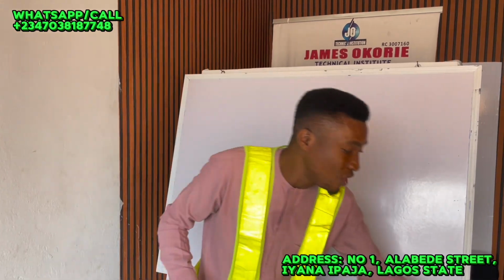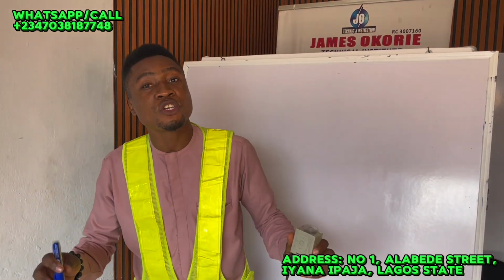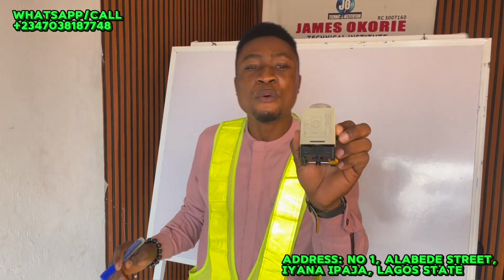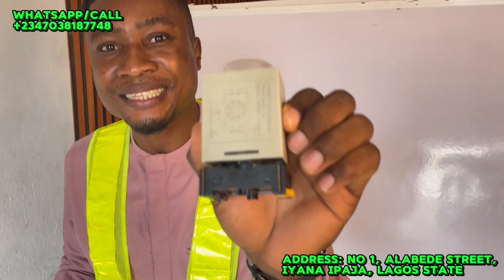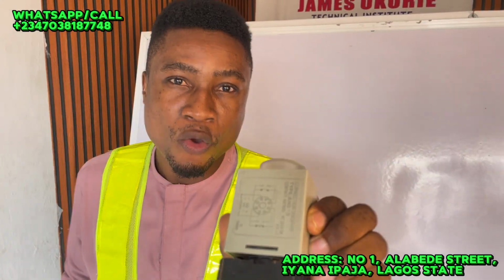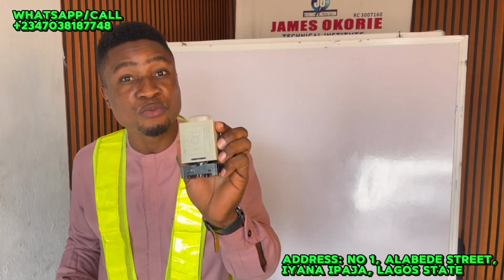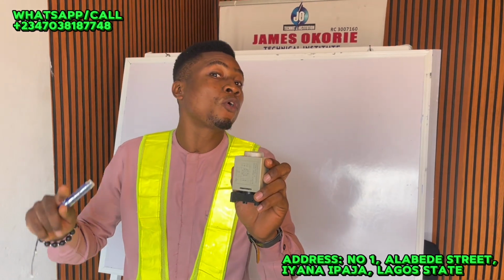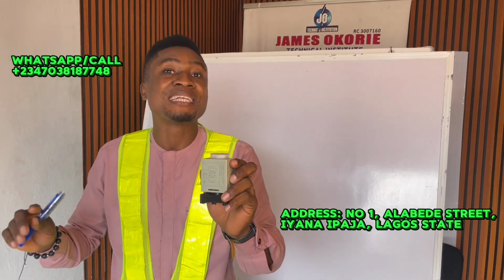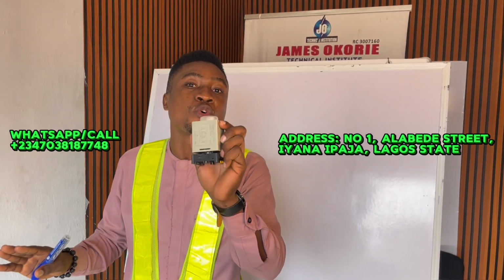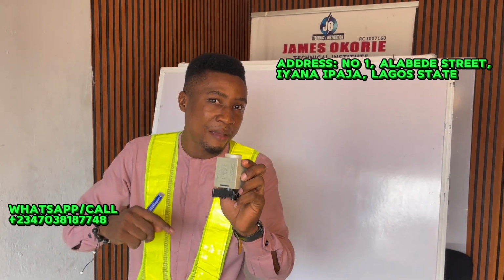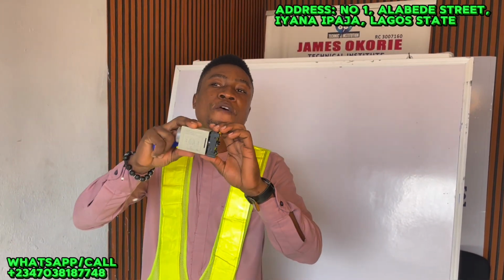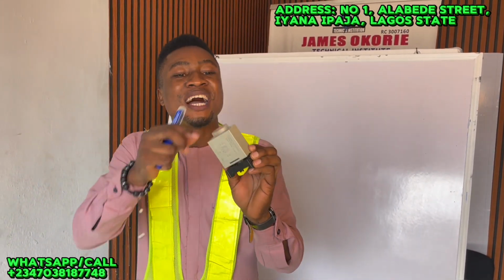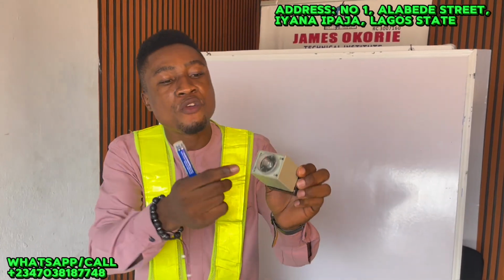So let's start. Today, we shall be discussing about timer. Here with me is a timer relay. What's a timer? We said that there are industrial switch gears which are being used to automatically control a load at a particular time frame. So you can use it to control a load depending on the set time that you set the timer, right?